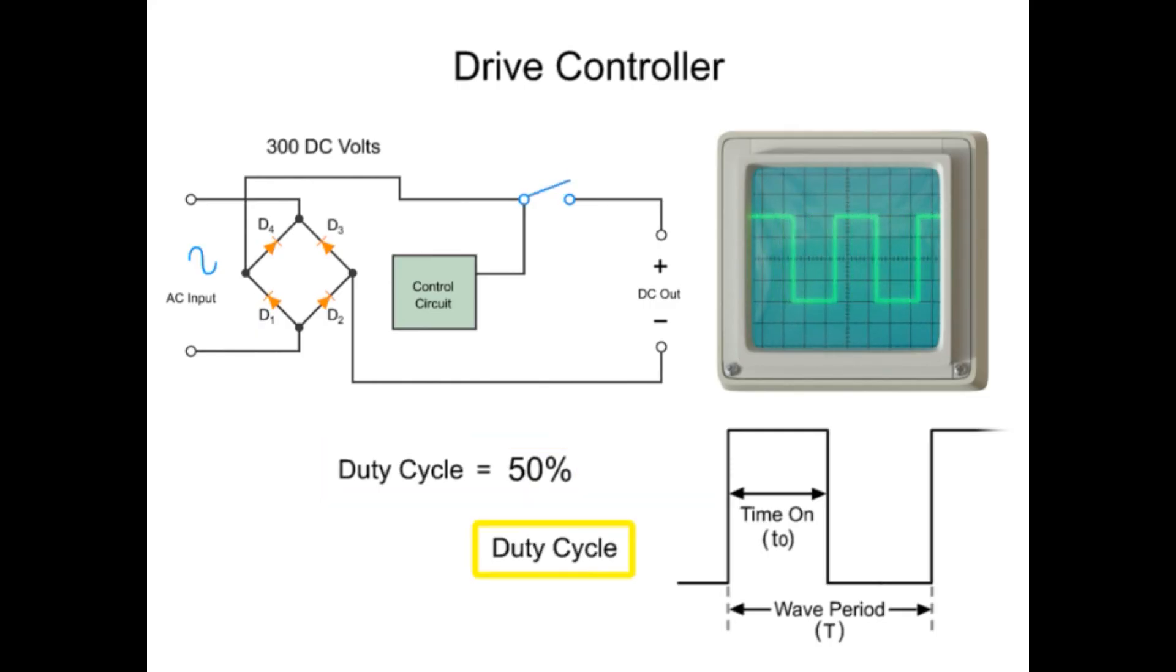Multiplying the duty cycle times the input voltage will give you the voltage output. In this example, a 300 volt input will be modulated by 50 percent, so the final voltage delivered to the load, or motor, is 150 volts. Thus, controlling the speed of a motor can be achieved by modulating the square signal waveform.